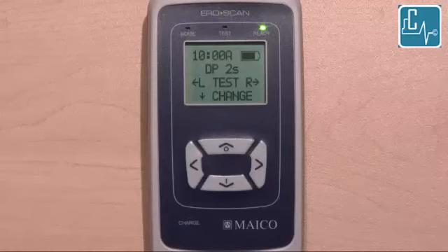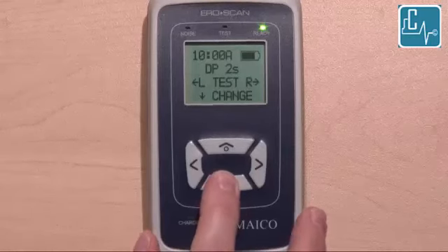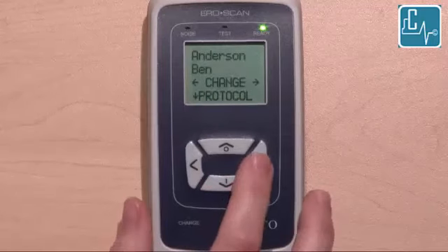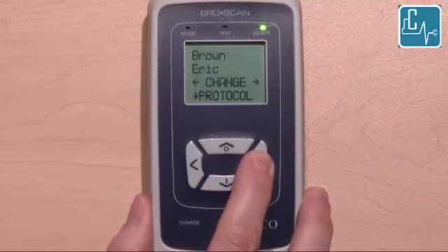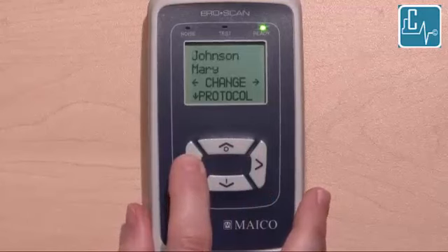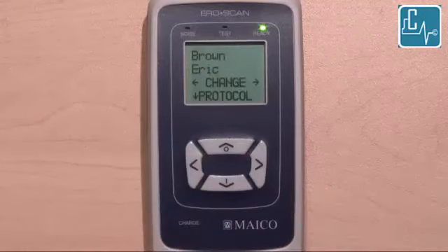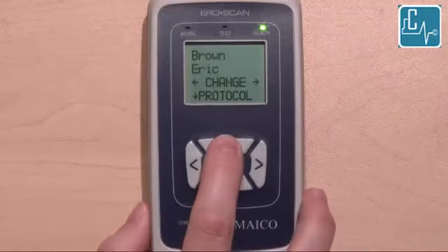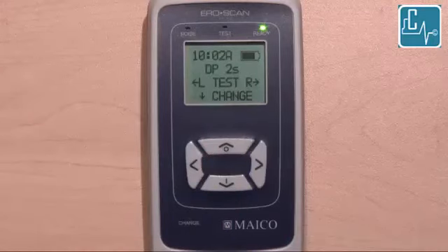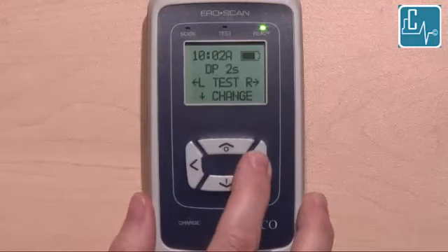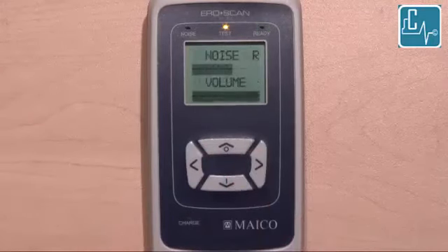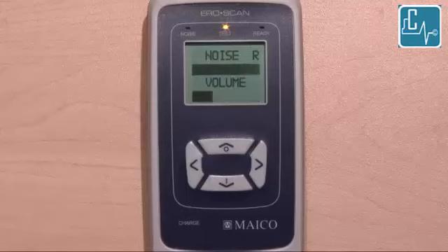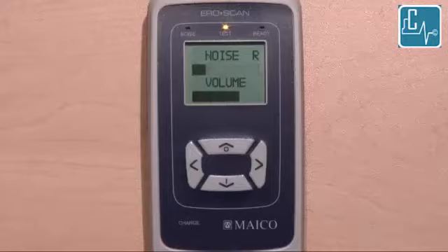When conducting a test using patient names, press the down arrow key, then use the right-left arrows to scroll through the names on the device. Once the test patient is shown on the display, press the up arrow key to reach the main test screen and select your test ear to proceed as normal. Please note that every test conducted within that patient name will be saved and thus can be downloaded into the database.